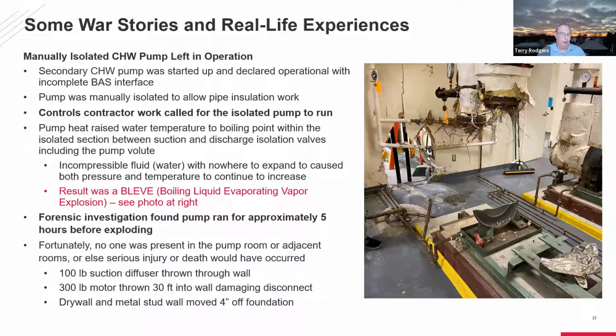The pump's completely isolated. Eventually it exceeded the boiling point, but because it had nowhere to expand, it just became a saturated steam type condition. Eventually the pressure and the temperatures rose. And my guesstimation, I don't know, it was about 200 PSI or so because the pump was rated for 175 pounds. So I'm just taking a guess. That equates to about 380 degrees Fahrenheit water. So when it finally ruptured, we had what's called a boiling liquid expanding vapor explosion, and a picture of the result is there on the right.